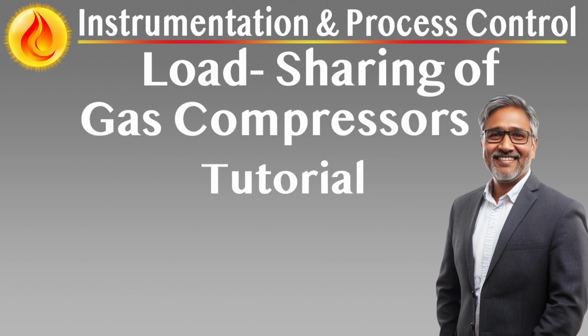Summary. The load-sharing instrumentation architecture for process gas compressors transforms a traditional control scheme into a predictive, synchronized, and surge-aware network. By intelligently distributing load, protecting individual machines from destabilization, and regulating pressure and flow with dynamic precision, this framework ensures maximum operational efficiency with minimum hardware stress.